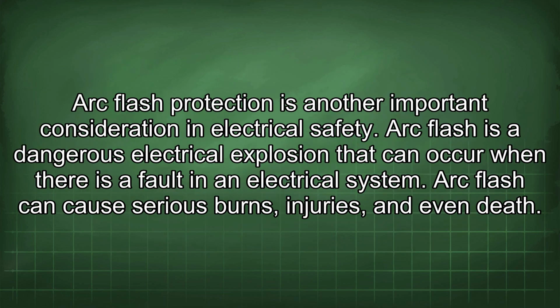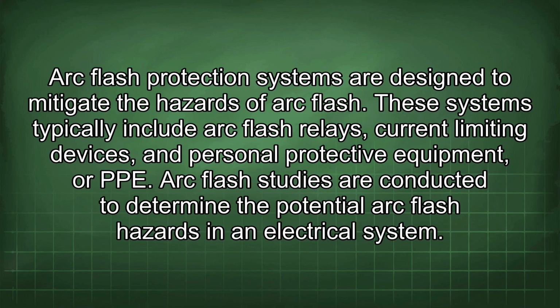Arc flash protection is another important consideration in electrical safety. Arc flash is a dangerous electrical explosion that can occur when there is a fault in an electrical system. Arc flash can cause serious burns, injuries, and even death. Arc flash protection systems are designed to mitigate the hazards of arc flash. These systems typically include arc flash relays, current limiting devices, and personal protective equipment, or PPE.